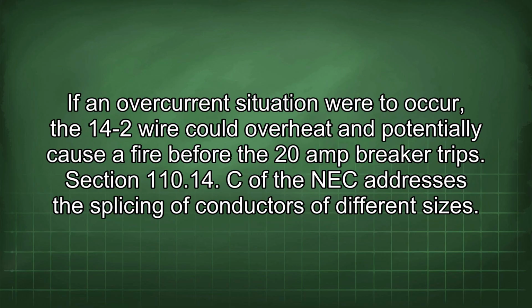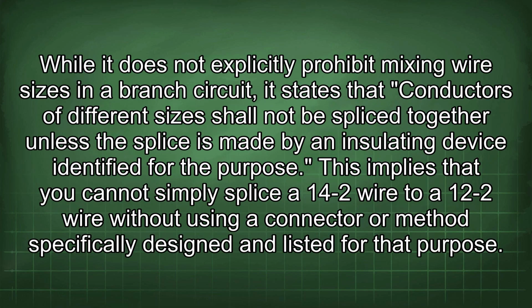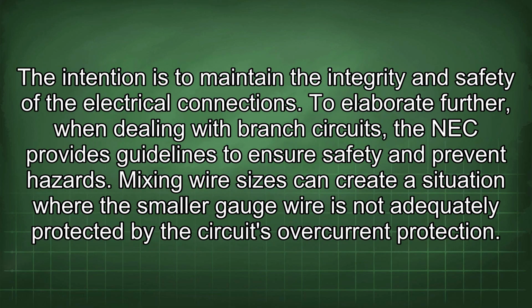If an overcurrent situation were to occur, the 14-2 wire could overheat and potentially cause a fire before the 20-amp breaker trips. Section 110.14(C) of the NEC addresses the splicing of conductors of different sizes. While it does not explicitly prohibit mixing wire sizes in a branch circuit, it states that conductors of different sizes shall not be spliced together unless the splice is made by an insulating device identified for the purpose. This implies that you cannot simply splice a 14-2 wire to a 12-2 wire without using a connector or method specifically designed and listed for that purpose. The intention is to maintain the integrity and safety of the electrical connections.